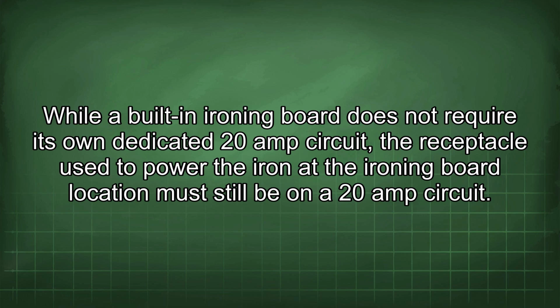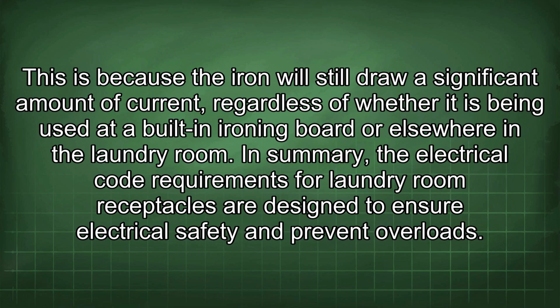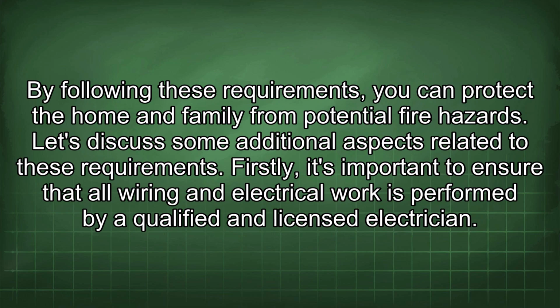While a built-in ironing board does not require its own dedicated 20-amp circuit, the receptacle used to power the iron at the ironing board location must still be on a 20-amp circuit. This is because the iron will still draw a significant amount of current, regardless of whether it is being used at a built-in ironing board or elsewhere in the laundry room. In summary, the electrical code requirements for laundry room receptacles are designed to ensure electrical safety and prevent overloads. By following these requirements, you can protect the home and family from potential fire hazard.